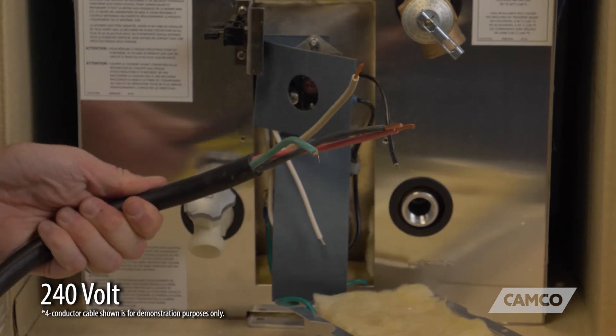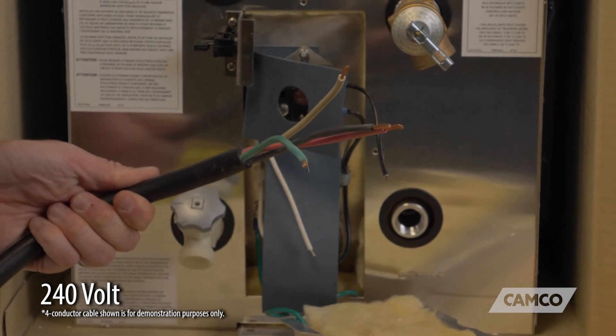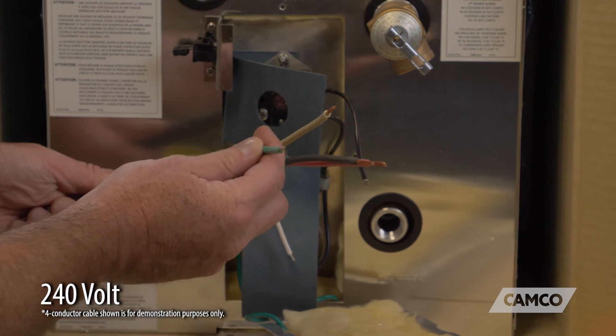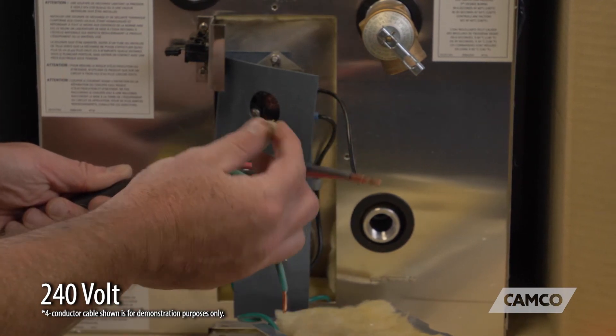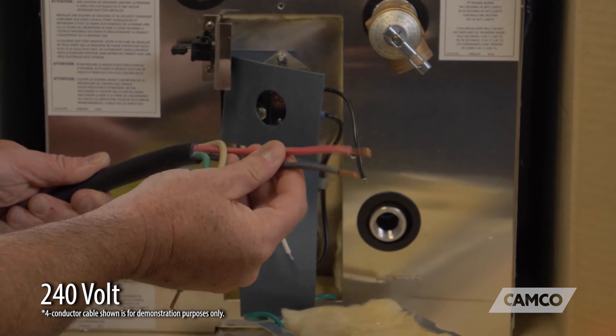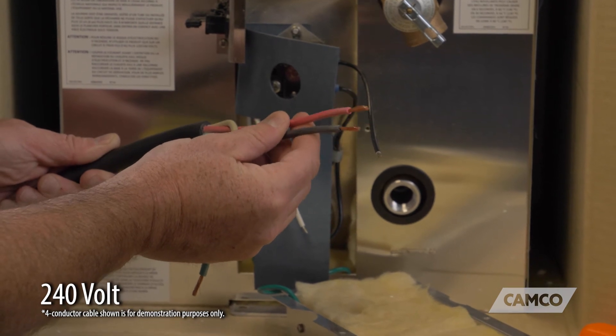This is typically what the wire is going to look like coming into your water heater from your boat. It's a four conductor cable. We're going to have green for ground, we're going to have white for neutral, and we're going to have two hots, a red and a black typically.